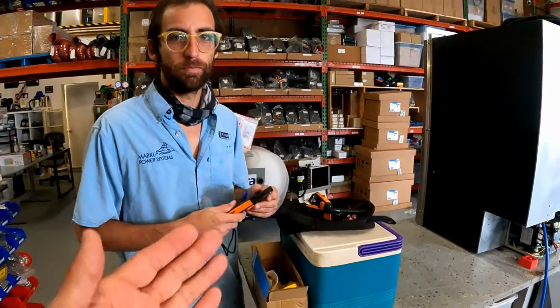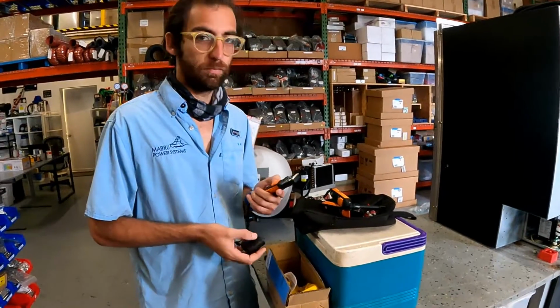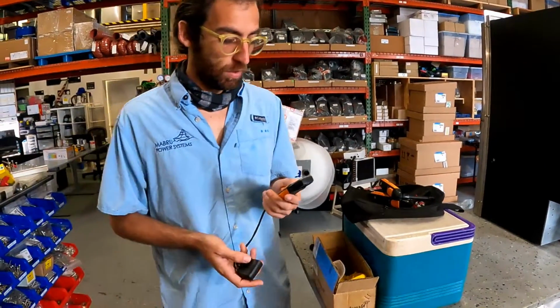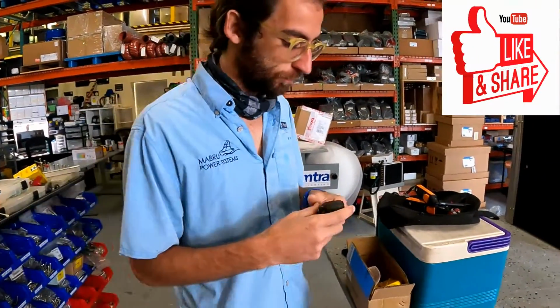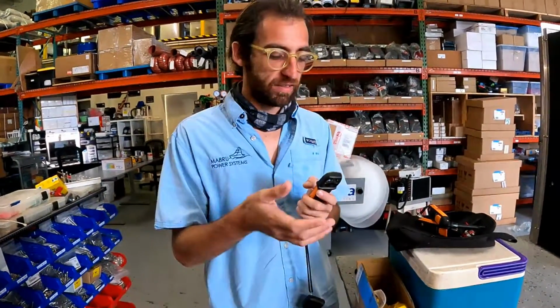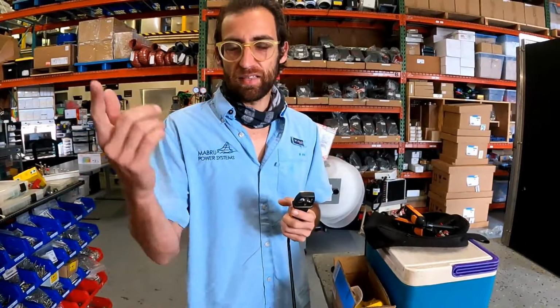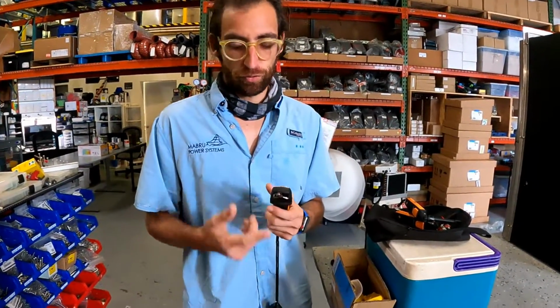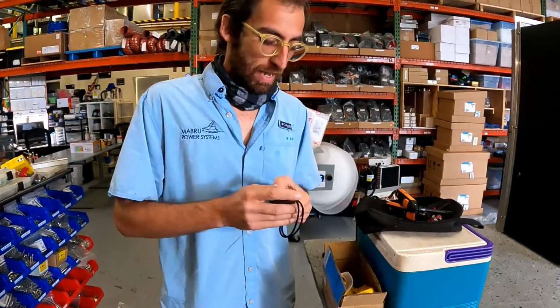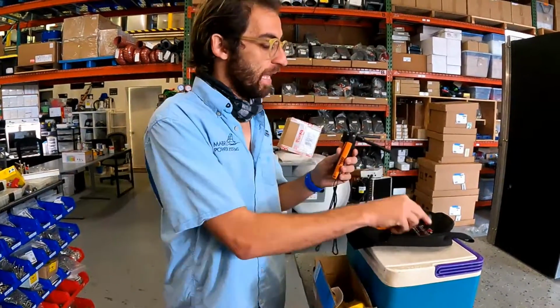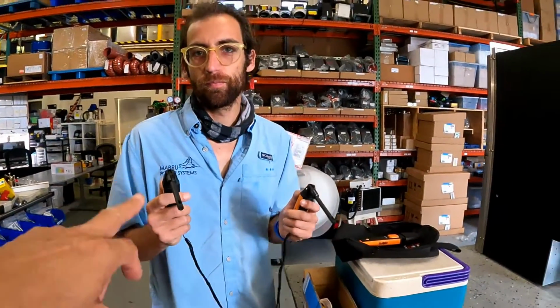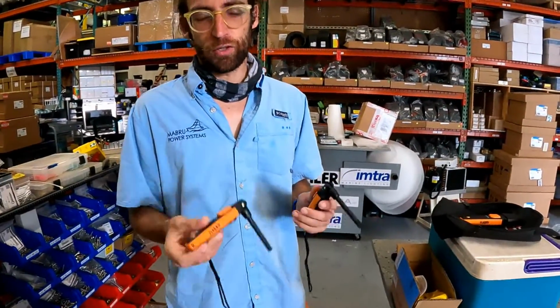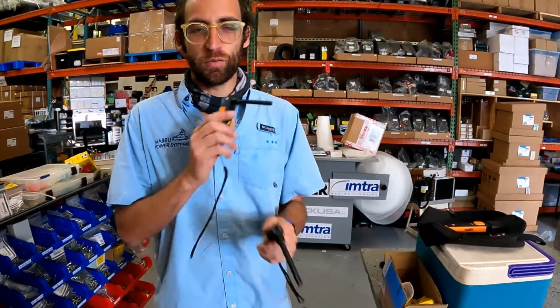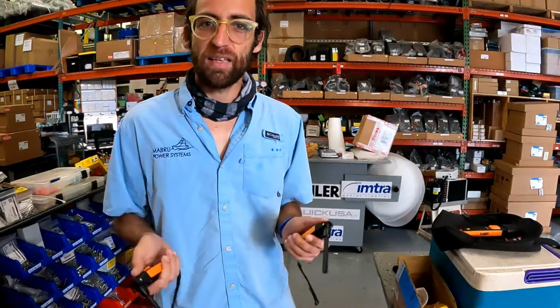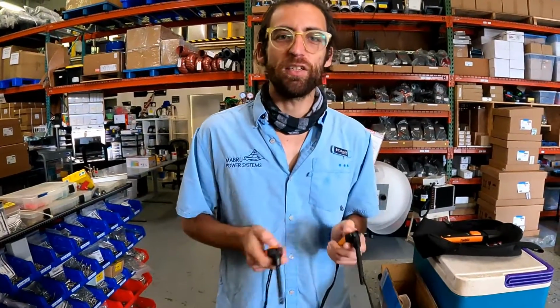We are going to use that equipment to calculate the BTUs of the equipment. Here we have the anemometer. We're going to tell the app on the phone what size the exit of the unit is, and it's going to tell me how many CFMs the unit is producing. Once I have that number, I'm going to enter it into the system, and then I'm going to enter these two probes, one at the output on the return, and one on the supply. It's going to read the delta difference, as well as the humidity difference, and it's going to be able to calculate how many BTUs the unit is producing.